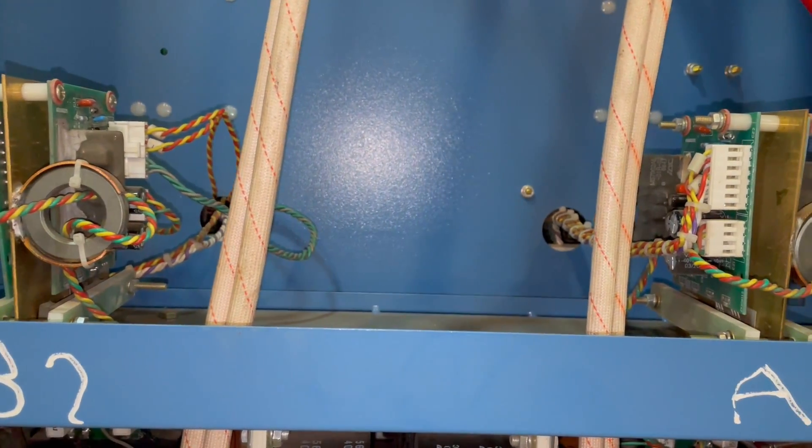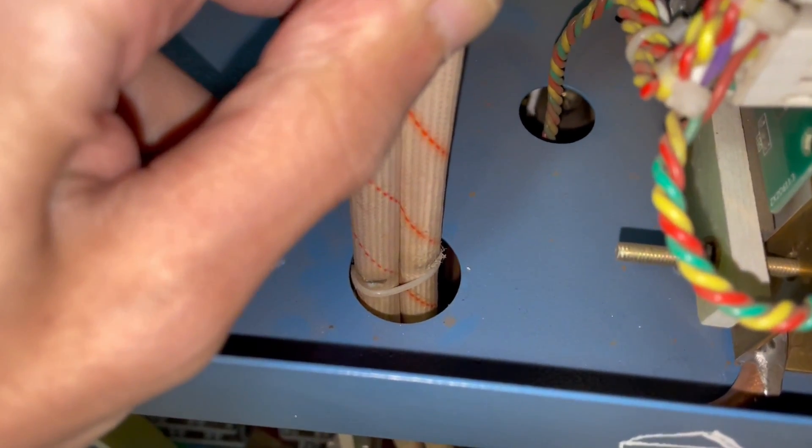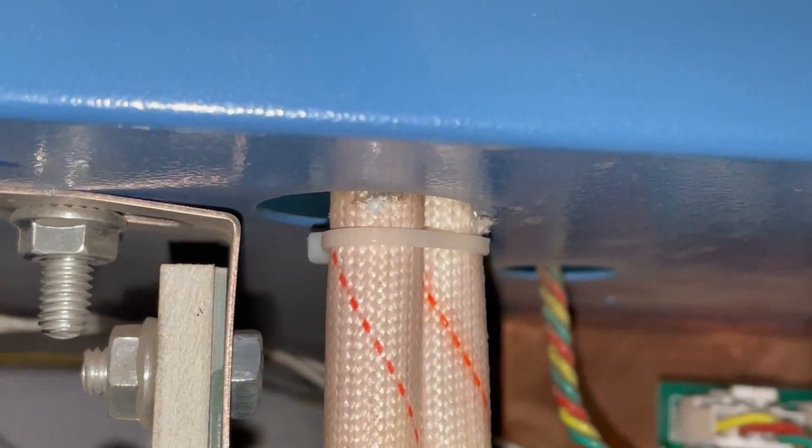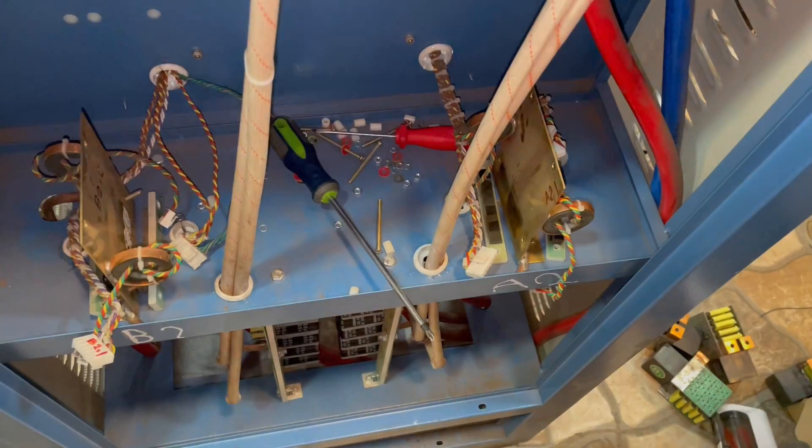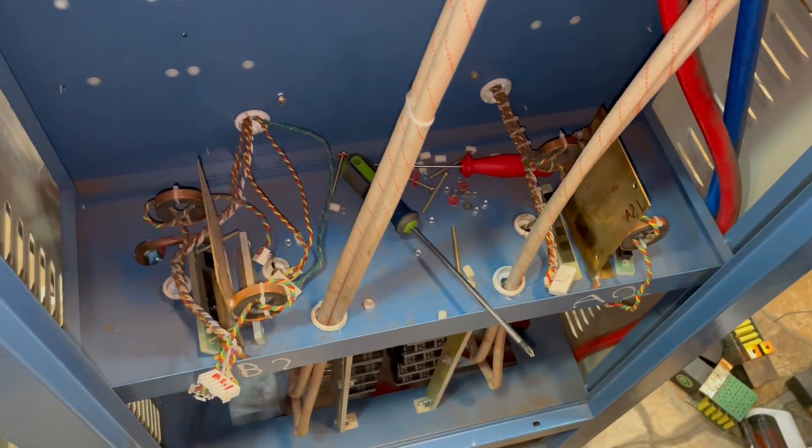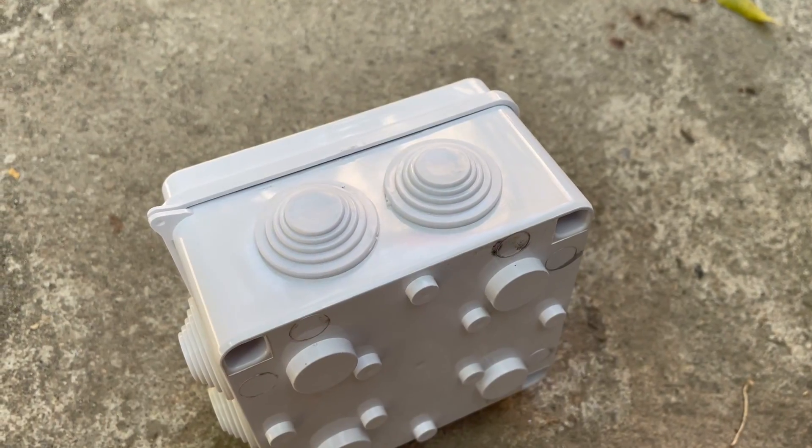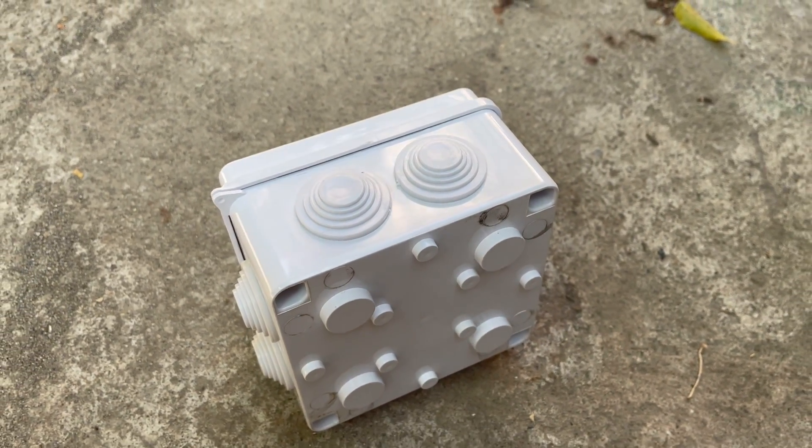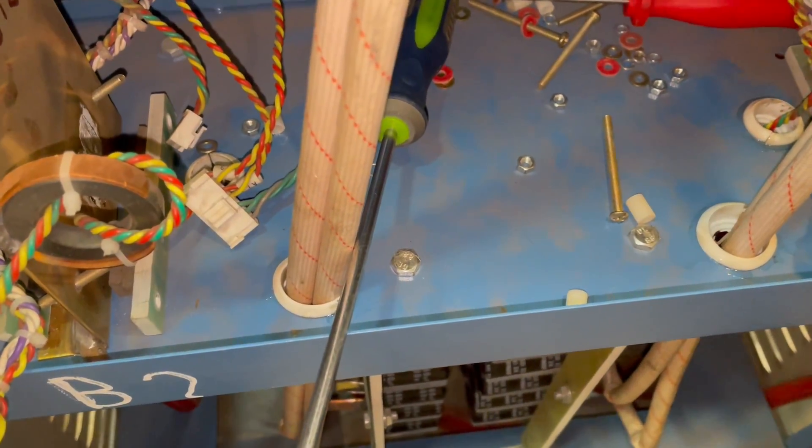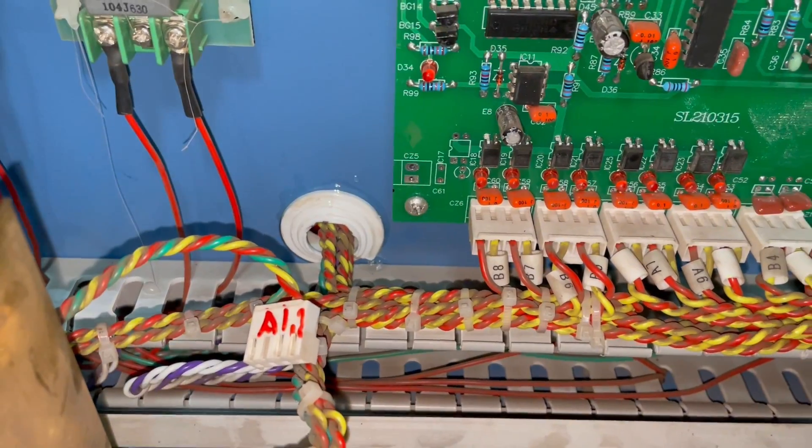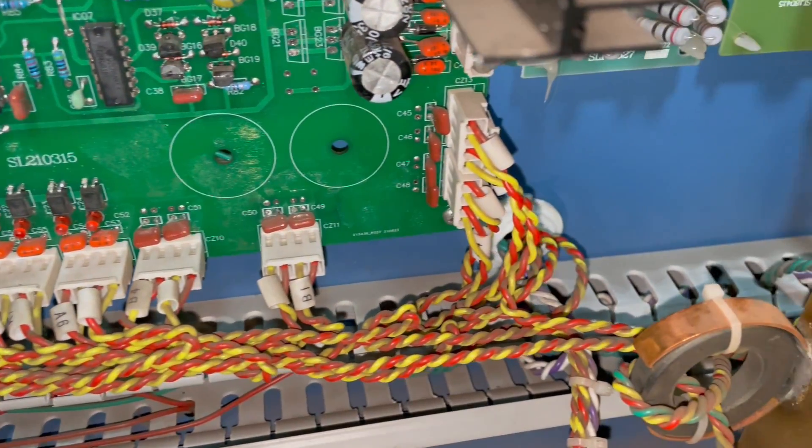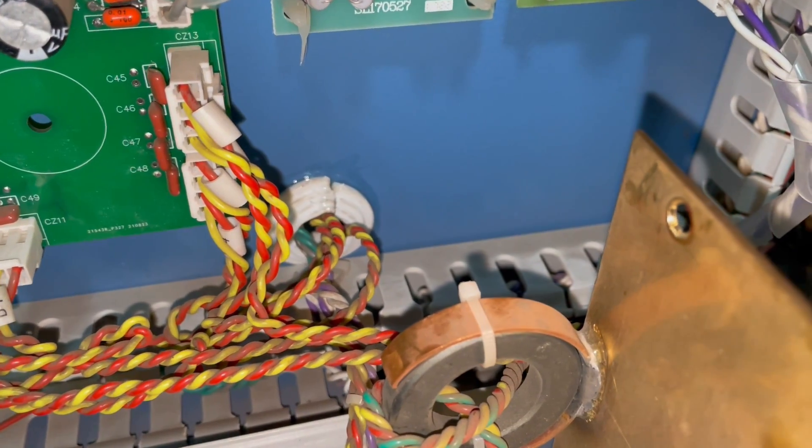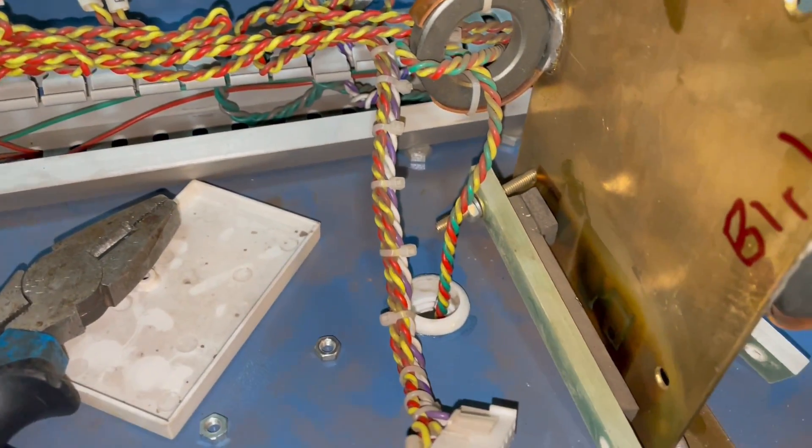In the first video I pointed out that not everything is good with the insulation. The power buses which are under high tension are in contact with the sharp edges of the holes in the housing and their insulation has suffered. I solved this problem with rubber insulators from junction boxes. In addition, these insulators are glued to the housing. In all the holes through which the wires go there is already reliable insulation. The input part is also isolated where phases were pressed against the metal housing.